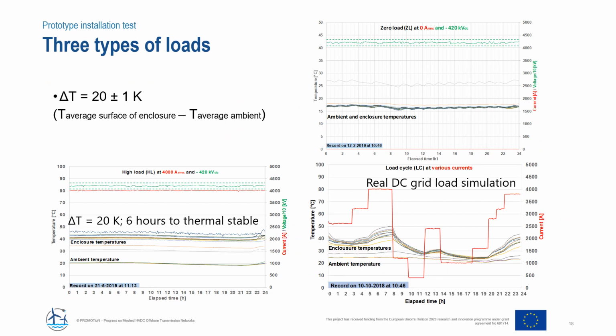So a bit more about the three load cycles now with measurement results. This is taken randomly, for example, measurements for 6 hours of temperature and current at high load, which is what you see on the left side, bottom graph: 4000 amps of current under 420 kV DC voltage. One thing I did not mention is that the long-term DC voltage was chosen to be 420 kV. This is to compensate for the long-term aging effect of HVDC GIS under real application, because this test lasts for 1 year. To compensate, the voltage has been increased by 20% more than the rated continuous voltage mentioned at the beginning.